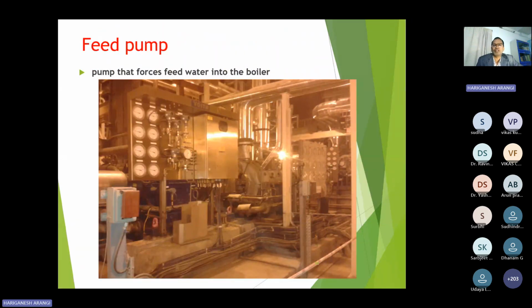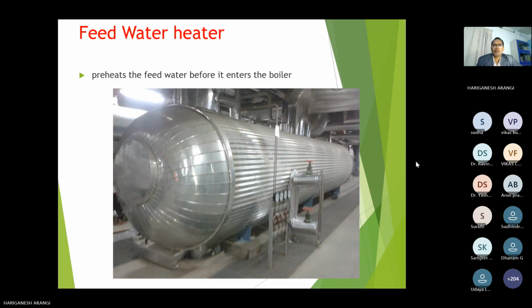This is the boiler feed water pump, where the water is pumped to the boiler. There will be feed water heaters to increase the efficiency of that water before sending it to the boiler. After the boiler feed pump, it will pass through a heat exchanger, where steam taken from the turbine will heat this feed water, and it will be pumped to the boiler economizer. When water with a 10-degree higher temperature goes to the boiler, you are saving fuel combustion, a quantity of fuel. So this is to increase the efficiency.